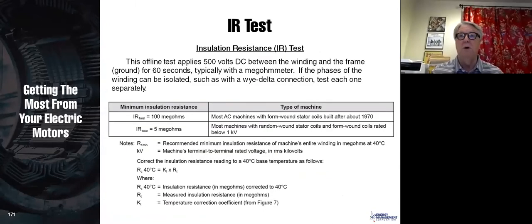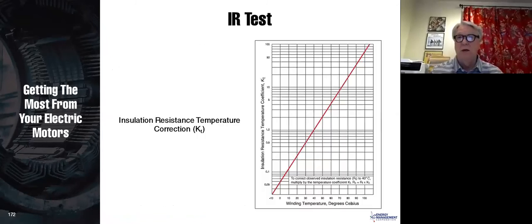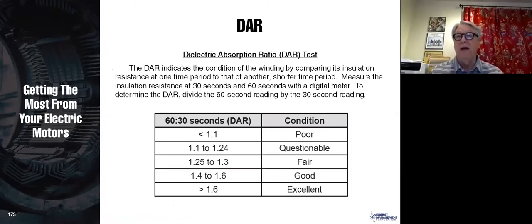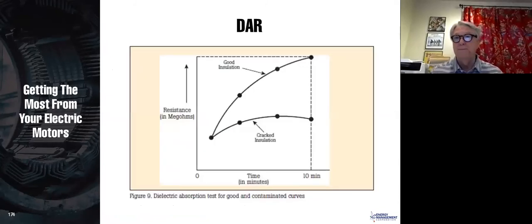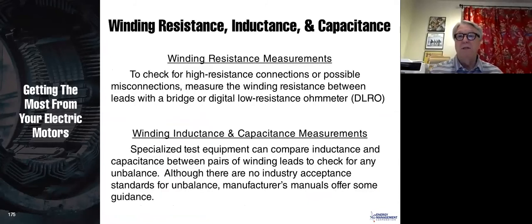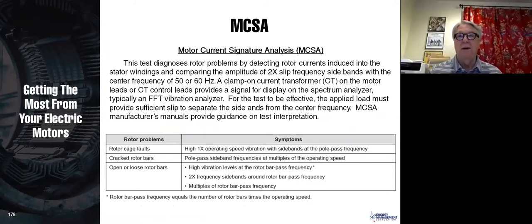Here's an IR test, the insulation resistance test. This you can find in your booklet. It tells you all about that. Here's your dielectric absorption ratio test. And again, it tells you what's acceptable, what's not, and that's all described in your book. Winding resistance measurements, winding inductance, and capacitor measurements.